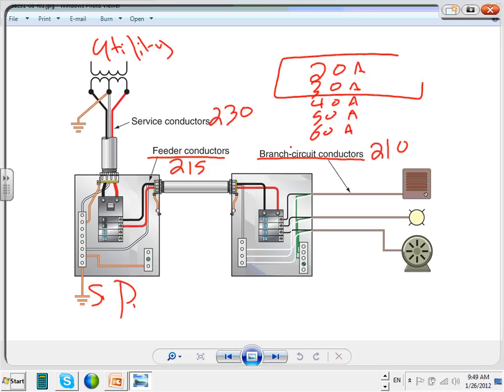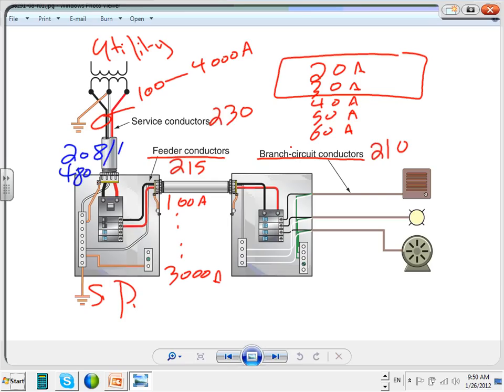Commercial lights and receptacles are probably sitting on 20 amp and 30 amp branch circuits. Feeders, my feeder here can be a 100 amp feeder all the way to probably 3000 amp. And the service here can be from 100 amp all the way to 4000 amp. That's what we do in Minnesota. They can allow you to go up to a 4000 amp service coming into the building. Make sense? Voltage wise, guys, commercially most likely 208 here, or 480 with 120 and with 277.